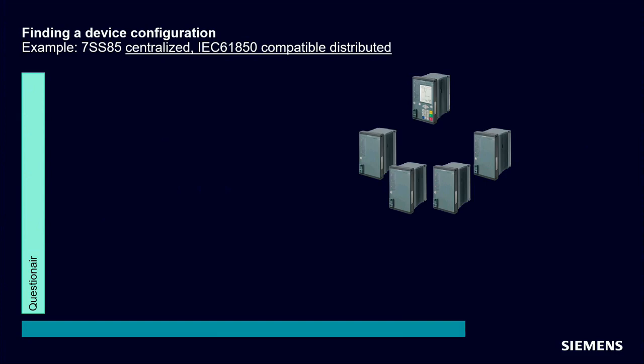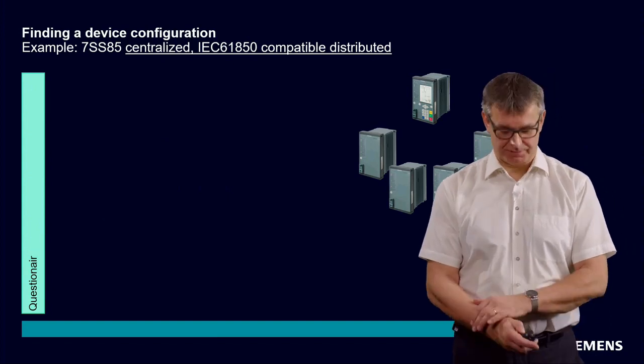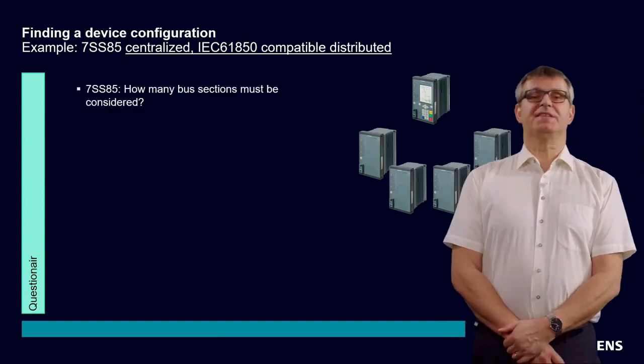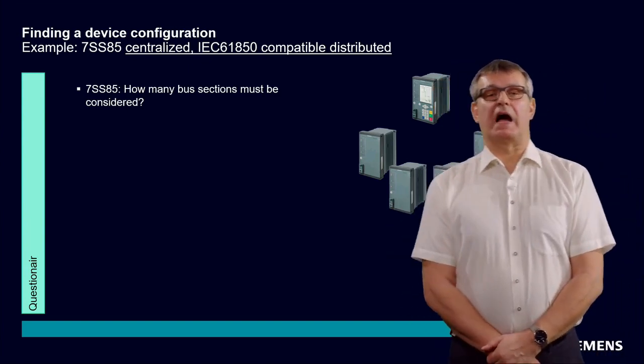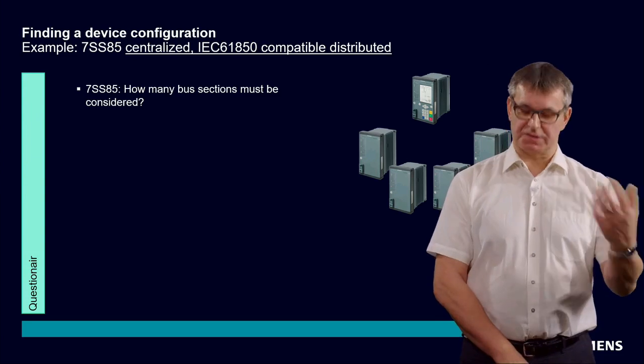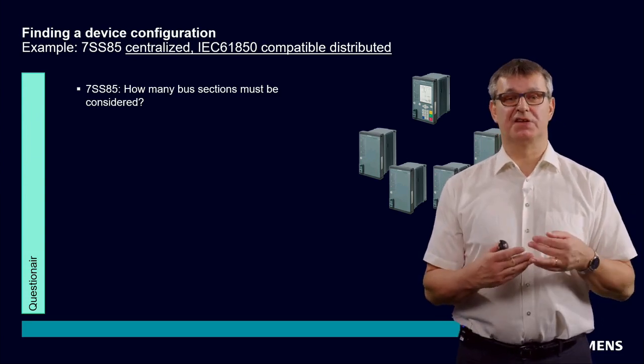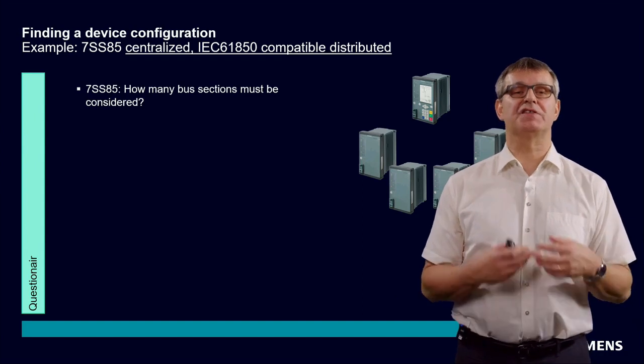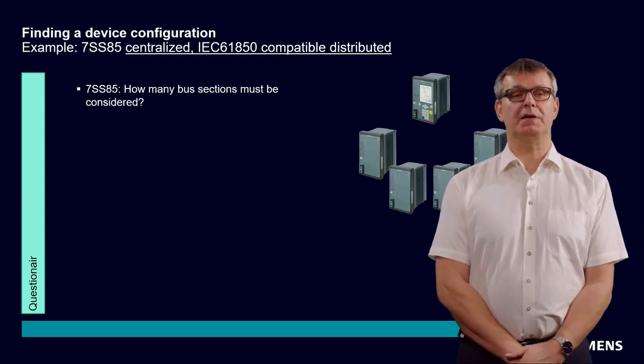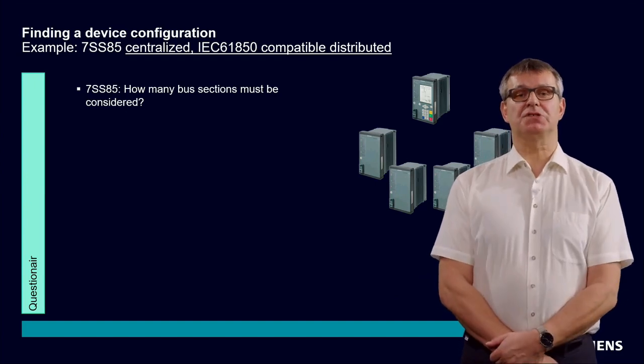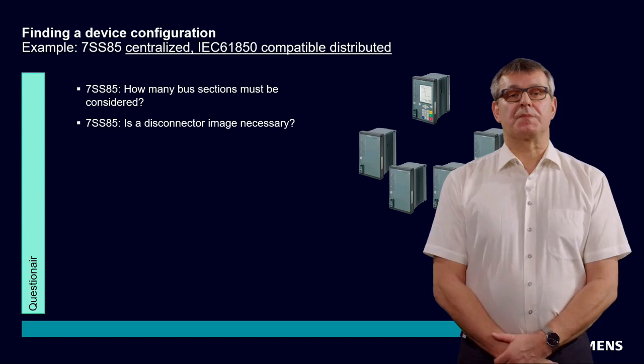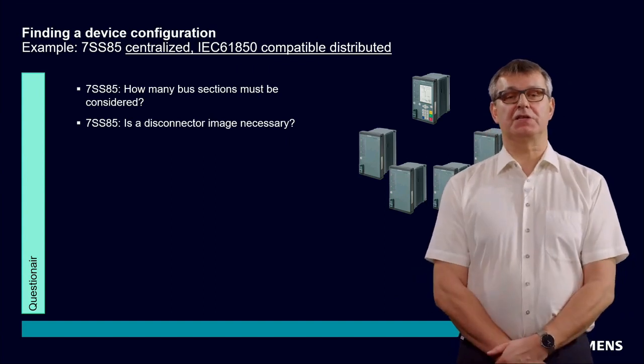So last but not least, how to configure the 7SS85 IEC 61850 compliant distributed solution, which uses the centralized types of the 7SS85. It's a little bit of a mix. So how many bus sections must be considered? The answer for the 7SS85 is the same as for the centralized busbar protection, so you have the same types and the same significant features available. You have to answer how many bus sections must be considered, and whether a disconnector image is necessary.